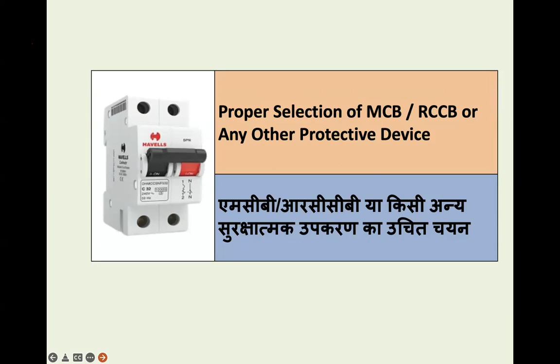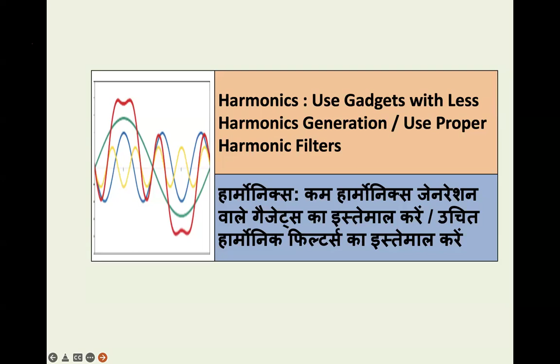Harmonics, I've already explained. We are using electronic gadgets: microwave, inverters, AC inverters, fridge, laptop, desktop. All these are generating harmonics. And we have to do a power quality check. Based on that, we have to select the size of the neutral. We have to reduce the hazards because of overheating of the conductor because of harmonics.